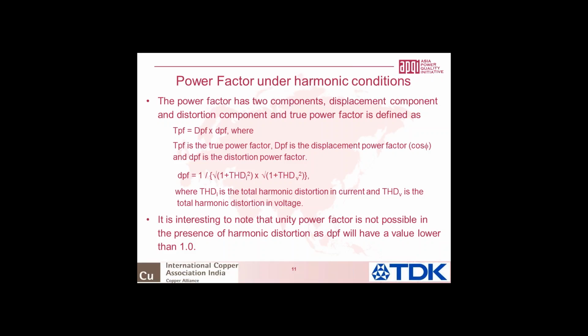And the displacement power factor equation is the same as in the case of a sinusoidal system, but the definition for the distortion power factor is what you would see in this equation, which is 1 upon root of 1 plus THD I square, into root of 1 plus THD V square, where THD I and THD V are the total harmonic distortion of current and voltage respectively. And it is interesting to note that you will never be able to achieve unity power factor even if you have 1% voltage or current distortion, because it's 1 plus root of some percentage square. So even if I have 1% THD in voltage, I will have 1.001, which means the entire concept of the so-called madness for achieving unity power factor needs to be relooked at.